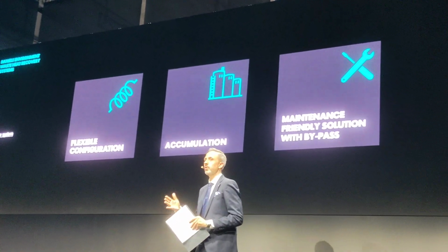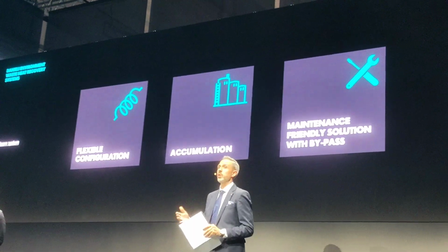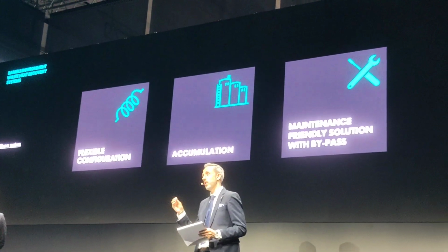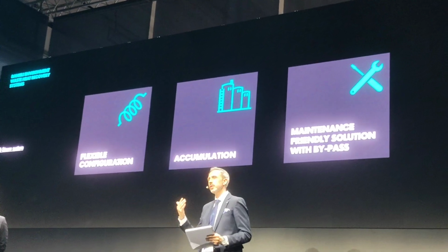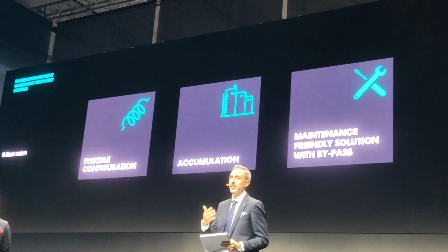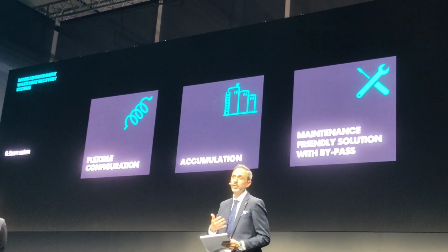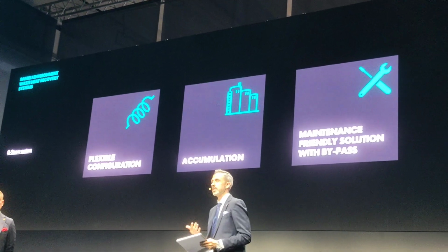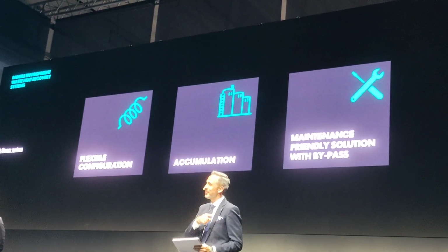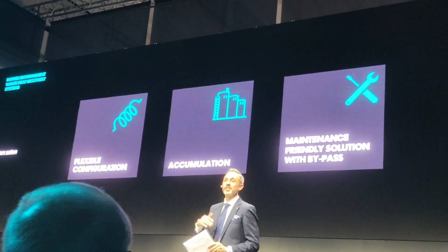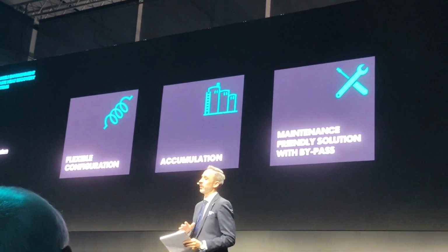And this is possible, for example, by installing a quenching tower in the bypass line, so the primary fumes cooling is anyway provided, with also the additional beneficial effects given by the fast cooling provided by the quenching tower itself. And in Danieli, spoiler alert for the next presentation, we have developed several interesting configurations for the quenching tower.